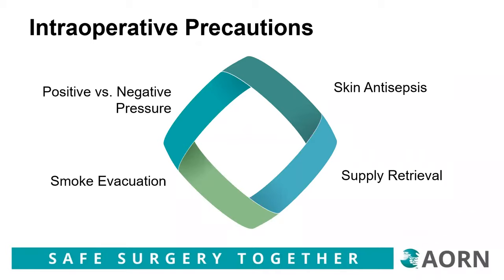Regardless of the type of airflow used, if the patient is intubated in the OR, allow sufficient air exchanges to remove air contaminants before personnel who are not wearing an N95 or PAPR re-enter the room after intubation. The time for this to occur depends on the number of air exchanges. For a room with 15 to 20 air exchanges, it will be around 28 minutes. Consult with your facilities management team to determine the specific time for your facility.